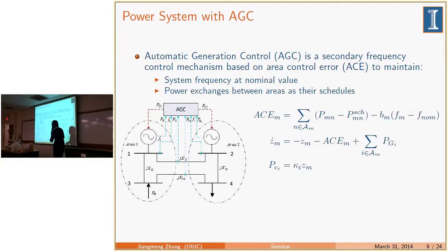AGC takes measurements from the power system and calculates the ACE, area control error, which is basically the mismatch in frequency as well as in power exchanges. Then AGC calculates the control variable PCI based on the ACE, and sends the control command back to the power system.